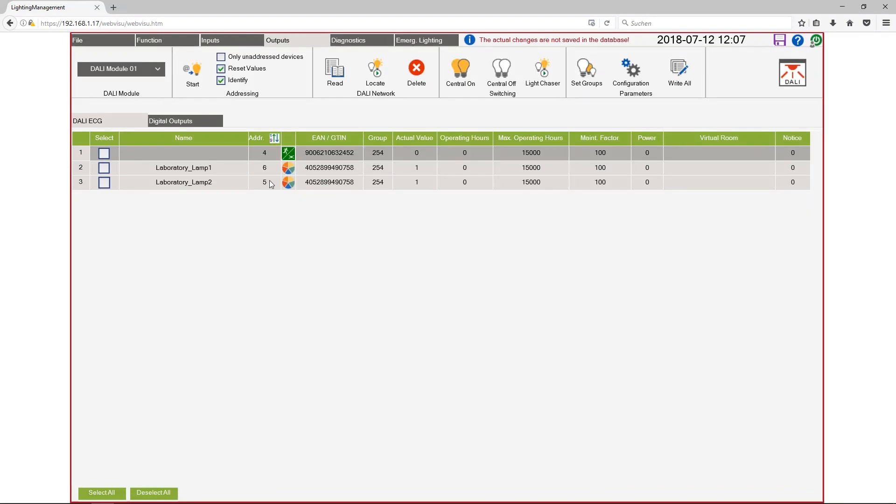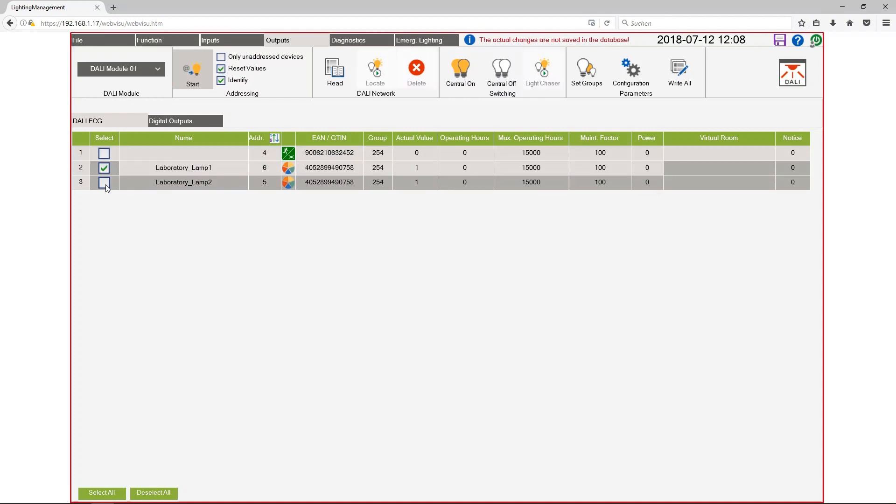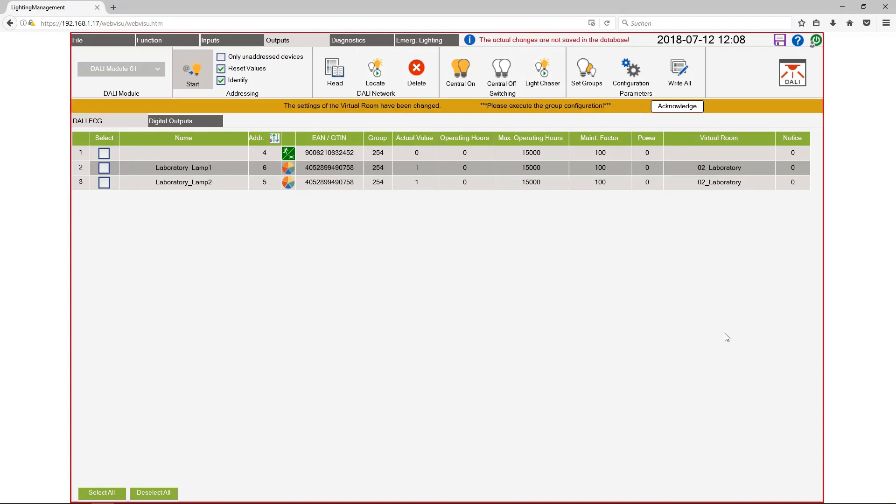Let's take a look at the outputs. Here we have our two tunable white lamps. I have addressed these lamps before by clicking on start and type in the name. Now I want to assign these two lamps to the virtual room laboratory. I get the message I have to click on set groups. So I will do it. And in two seconds the settings are saved in the ECGs.